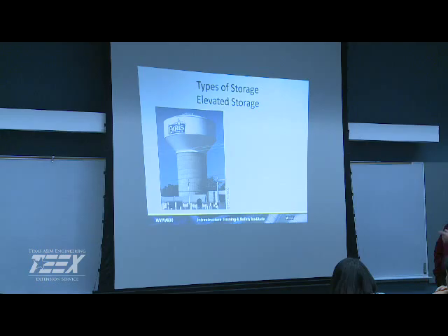Elevated storage. So anything up above, this part here is just going to be piping and stuff, access up into it, and then all your storage is up on top. Anything above the 80 feet is going to give you your pressure. One of the things about elevational head, it doesn't matter if it's 1 inch in diameter or 100 foot in diameter, it's not the volume, it's the height of the water that gives you the pressure. So by having the water stored up high, 80 feet above your highest connection is all considered elevational.